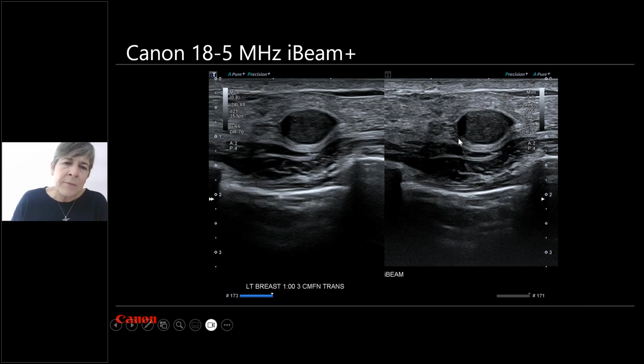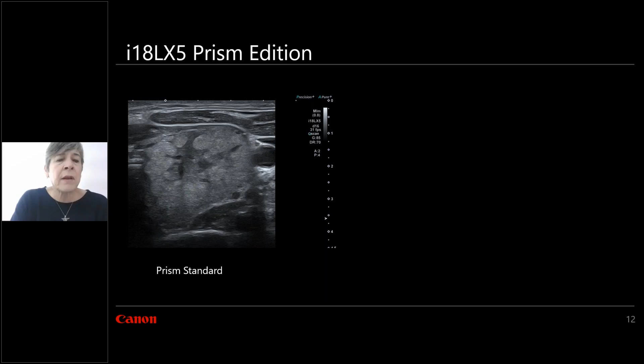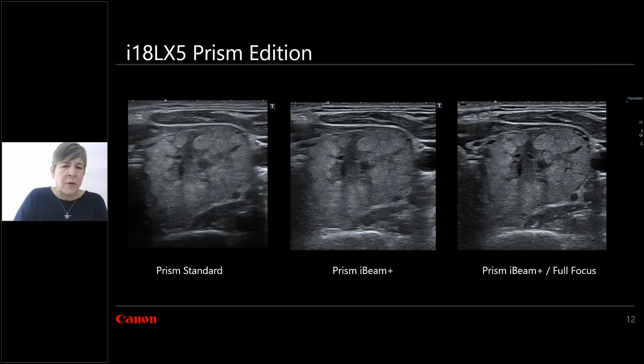Now I know this is not a breast image, but this is a thyroid, and it's going to show you the progression that we have with the Prism Edition. In standard imaging, you can see this large thyroid nodule, with great visualization of the muscle. Once I go into iBeam Plus, you're going to have an increase in your penetration. Look at how much better you're seeing the muscle in the far field. Once you are in iBeam Plus, you have the ability to go to a full focus mode. So instead of having focal zones, you can have the system do all the focusing for you. Once again, we give you that ability to choose that option. It's not something that you're stuck with.